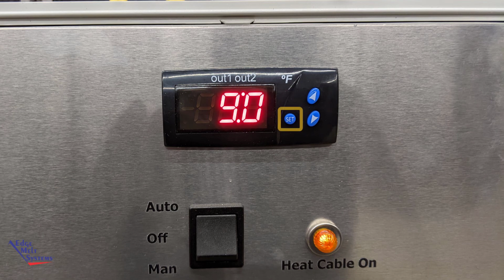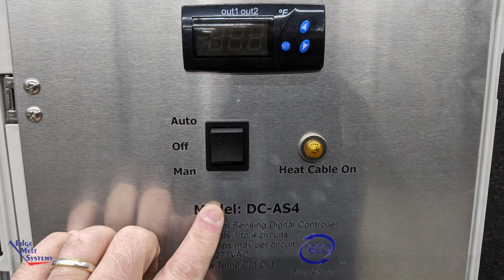When done, hit that set button once again, and those values will be flashed into memory. There's no additional saving that needs to be done. They will be immediately flashed into memory. Once all testing, setup, and adjustments are complete, the panel can be returned to the center position on the 3-position rocker switch, or the off position. It's now ready for customer use when needed.